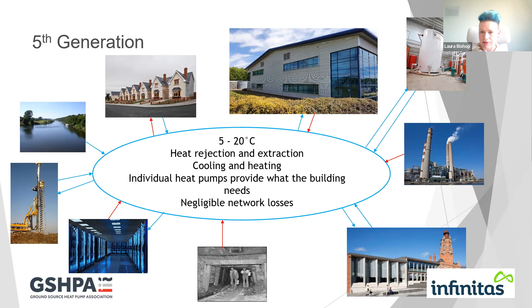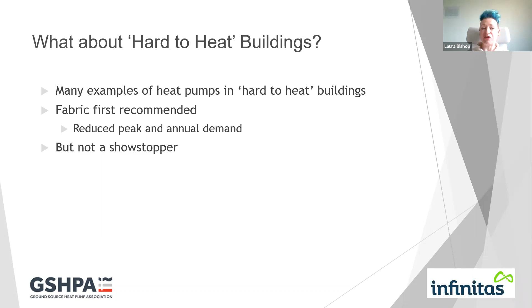So what about hard to heat buildings? People always say we need cavity wall insulation, loft insulation, double glazing - but there are stacks of examples of heat pumps being used successfully in those difficult buildings. Fabric first is recommended because you reduce your peak and annual demand, so you can have a smaller heat pump. But if you can't do that, it's not a showstopper - I always refer back to places like the National Trust who've got heat pumps installed in their stately homes. They are completely grade 1 listed, can't do any fabric improvements, but they have heat pumps working very efficiently and effectively.